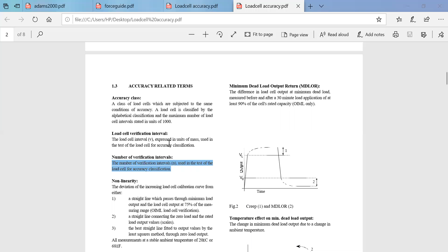And the next term you have to understand is the number of verification intervals. How many intervals should there be in measuring using a load cell in a single stretch? It is the number of verification intervals used in the test of the load cell for accuracy classification. You have to justify the number of intervals you are providing and how frequently the intervals change. This will go on a trial basis until you optimize the verification interval and the number of verification intervals. Once you end up with fixed numerical data, it goes on with a similar thing for n number of measurements. Initially you have to do a trial version until you get an optimized way of bifurcating the verification interval and the number of verification intervals, which helps in classifying the given accuracy of a load cell.